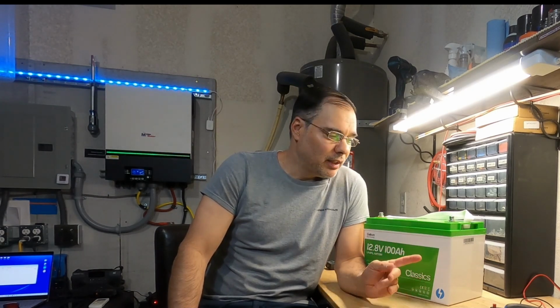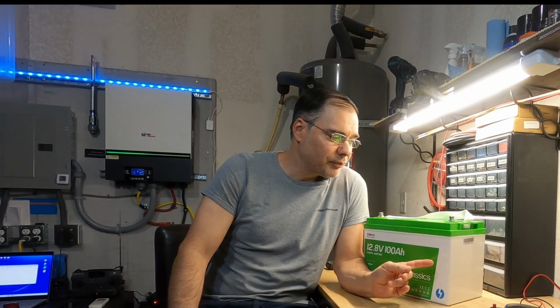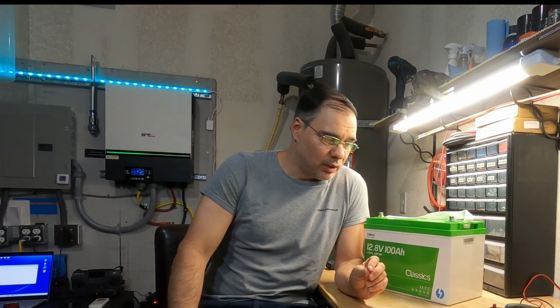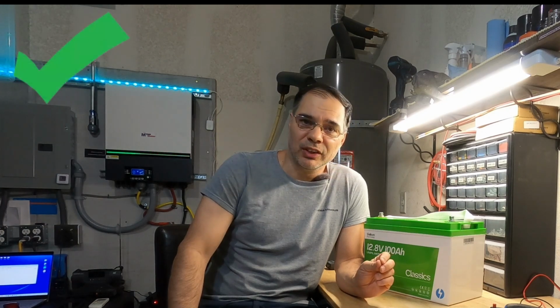Okay, so in some batteries, the BMS, if it detects a short circuit, will remain off for 30 seconds or 5 minutes, or it just depends on whatever the configuration of the BMS is. This one appears to stay off, well, at least as long as I tested it. As long as the short circuit condition exists, the BMS cuts the power off. As soon as you remove the short circuit condition, the BMS restores the power.